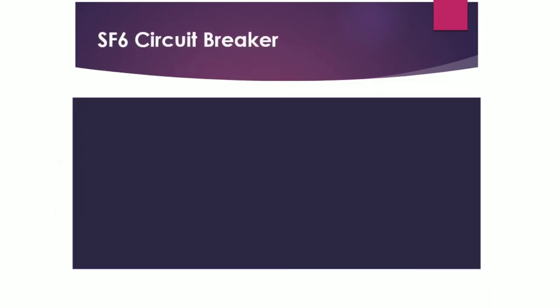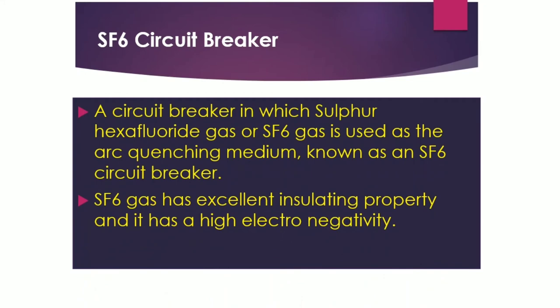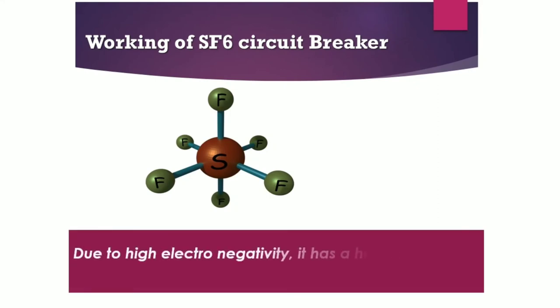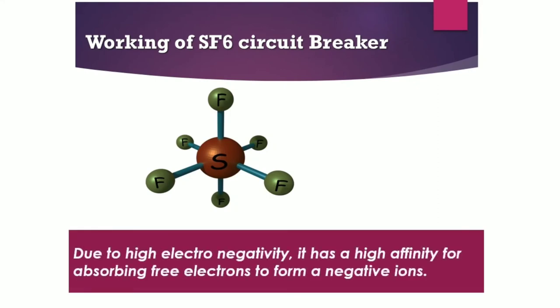The SF6 circuit breaker uses sulfur hexafluoride (SF6) gas as the arc-quenching medium. We use SF6 in this application because it has excellent insulating properties and high electronegativity. Due to its high electronegativity, SF6 gas has a high affinity for absorbing free electrons to form negative ions, which rapidly quenches the arc.